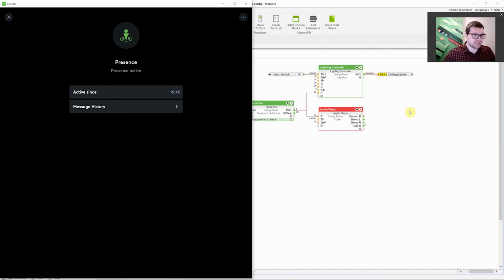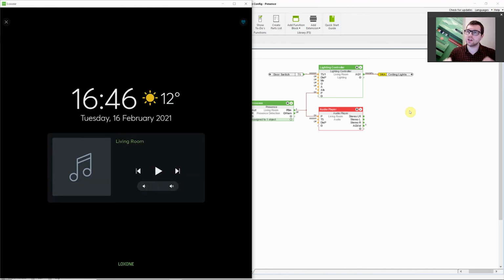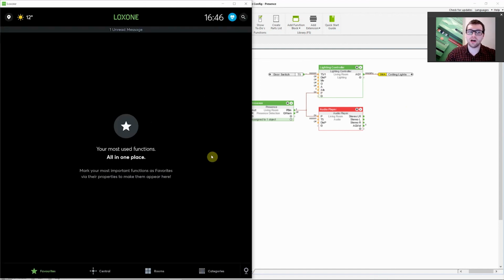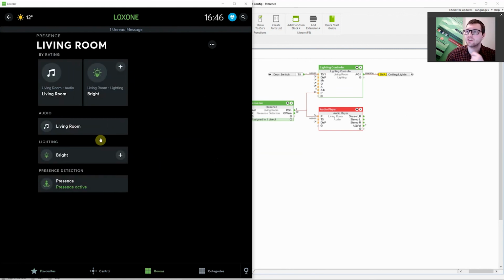So that is how the presence sensor and presence-based lighting works. Motion is the original trigger, and then even if you stop triggering motion, you can continue the sensor being active through an audible signal that is above your presence threshold. If you hit the TH timer within the presence block without an acoustic or motion trigger, the presence block goes off, which will in turn turn the lighting off if presence had brought the lighting on. You have 10 seconds after that point to reactivate the sensor through noise, which will then bring the lights back on. Otherwise, again, it has to be motion as the first trigger.